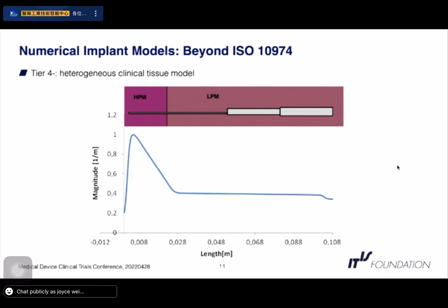But for example, a cochlear implant that goes inside the cochlea, most part of it is subcutaneous between the bone and the skin and the subcutaneous adipose tissue. So in this case, the new 10974 standard has a tier 4 clause in clause 8, which estimates the transfer function in a heterogeneous clinical tissue model, which can only be derived in simulation, because we can't just put two different liquids in the tank and scan, because they would mix. So what we would do is we measure the implant and the response at either of these tissues. Then we simulate the implant in either of these tissue simulating media as well. And we use this to validate the numerical model that we can derive of the transfer function, which we then use to develop this mixed medium transfer function model that can be used as an input to the IM Analytics medical device development tool.